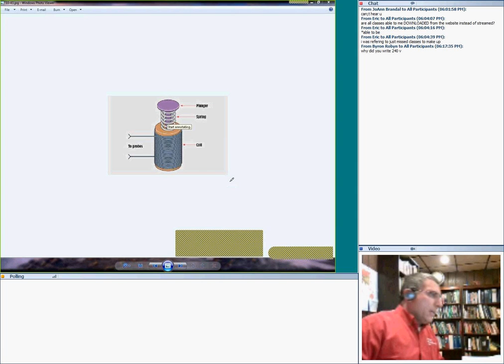All it does is if you bring a voltage right here to the voltmeter, suppose this is 240 volts, it has a plunger with an indicator here, and if it moves up to 240 here, be scaled up to 240 here, 120 here, say 40 volts here. That plunger moves up and down to indicate, and that indicator will move with it to show if it's 240, 120, just different levels. A lot of you guys use it just as an easy way of knowing if the equipment is hot or not. It's not accurate in terms of measuring the voltage - it just tells you is this voltage 480 or 240 or 120.